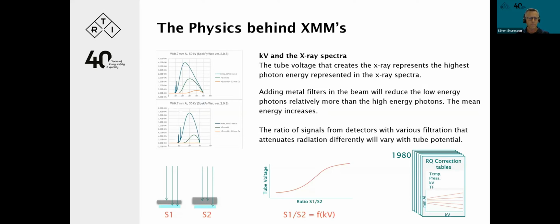showing how this spectra becomes affected by adding aluminum and copper, and that is pretty much what a kV meter does. Internally, it has a number of filters, and behind the filters there is a solid state detector or a detector that catches the radiation after the filters. That will generate a ratio, and the tube voltage can be described as a function of that ratio. And this will be valid if not varying anything else but the kV. Then this works perfectly. And the better slope there is on this equation or this ratio, the better resolution or precision you will have in the kV value.